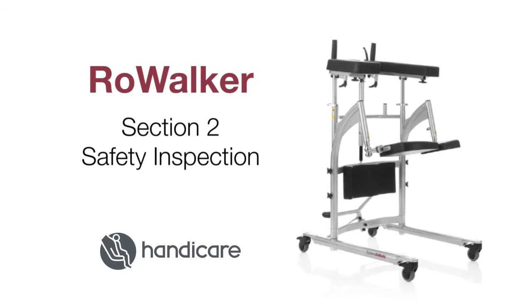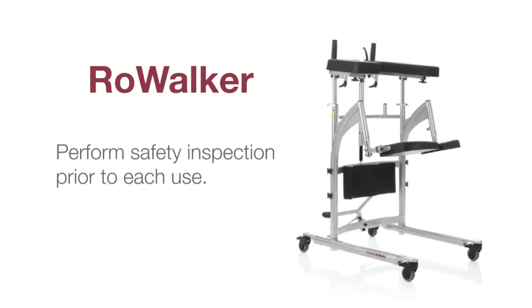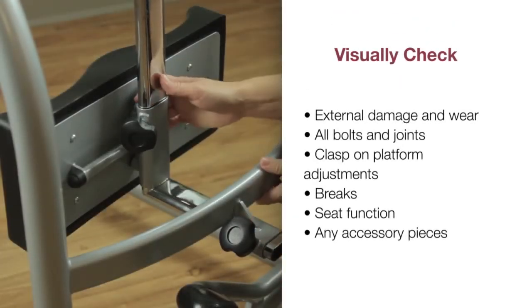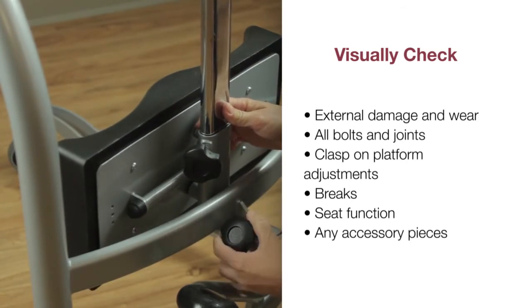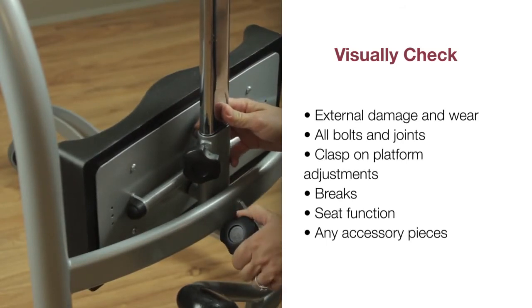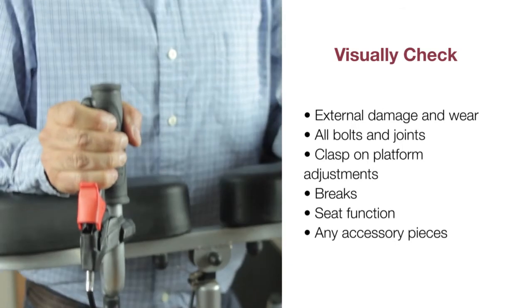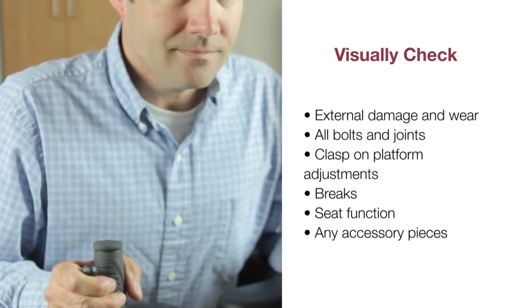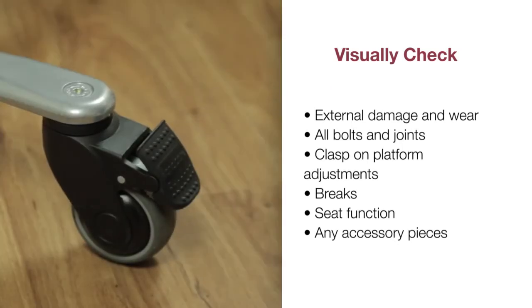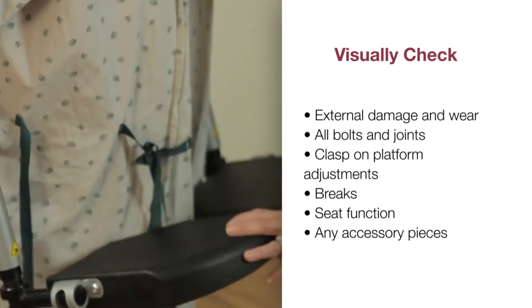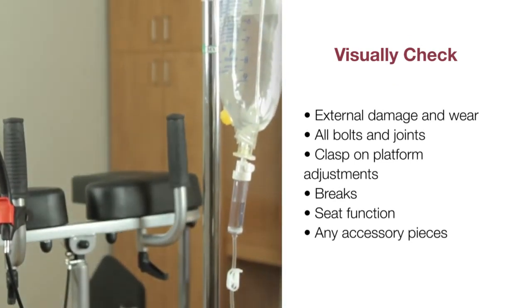For safe and trouble-free operation of the RoWalker 400, there are some routine procedures that should be performed prior to each use. Visually inspect the walker and check for any external damage and wear. Check that all bolts and joints are tight. Check that the clasps for the platform adjustment are present, movable and secured after adjusting to the desired height. Check the brakes for proper function and test the seats for proper function. Test any accessories for secure placement and function prior to use.